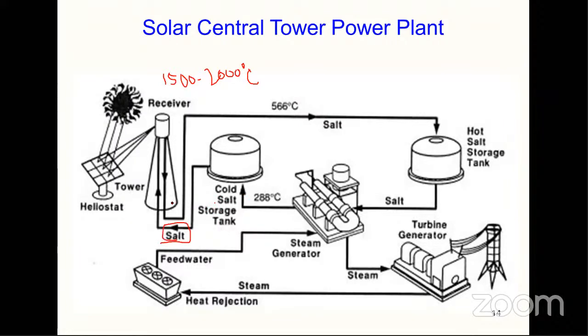Molten salt is circulated and stored in both cold and hot storage tanks. This is the hot storage salt tank, and from this the salt is circulated through a heat exchanger on one side, with the Rankine cycle on the other side. The high temperature salt gives heat to the water, turning it into steam, and superheated steam is generated in this evaporator, then goes to the turbine cycle and expands in the turbine. This is the Rankine cycle, and we need to reject heat via the cooling tower. The advantage is it can operate in two loops: the primary loop is the salt loop, and the secondary loop is the steam loop. The salt can be stored in big tanks so we can extend operations beyond sunshine hours.